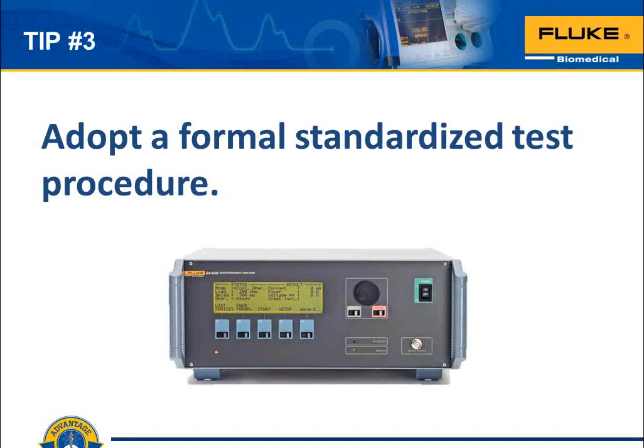It's important that the ESU functionality be quantitatively evaluated, not just qualitatively, by comparing it to the manufacturer's specifications or the requirements in applicable medical device standards. When the medical device manufacturer's specifications are not known, the IEC standard requirements are a reasonable substitute. And if you can't get a hold of the model-specific inspection procedure, then a category-specific test procedure may suffice, with the opportunity to add in some model-specific things as you discover them.